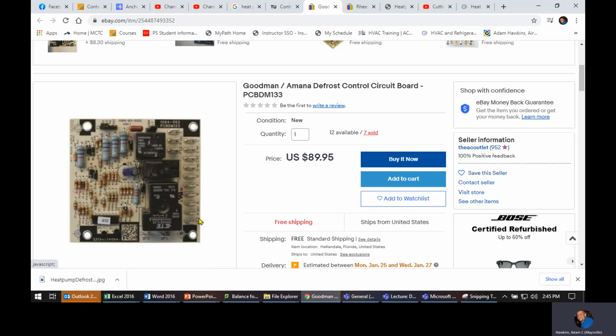And it says if this switch is closed, and it really doesn't check it, what it does is if this 24 volts is present, when it goes into that, then it sends it through the circuitry and it says, okay, we have power, we're going to run into defrost. But essentially it's checking the switch. So it checks that switch, assuming that DFT has 24 volts on it, 0 volts across, right? R to DFT, it's a switch, 24 in, 24 out, 0 volts across. That means the switch is closed, it's made, it's powered, sending power to the board.